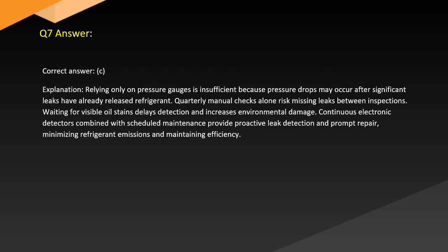Answer. Correct answer: C. Explanation. Relying only on pressure gauges is insufficient because pressure drops may occur after significant leaks have already released refrigerant. Quarterly manual checks alone risk missing leaks between inspections. Waiting for visible oil stains delays detection and increases environmental damage. Continuous electronic detectors combined with scheduled maintenance provide proactive leak detection and prompt repair, minimizing refrigerant emissions and maintaining efficiency.